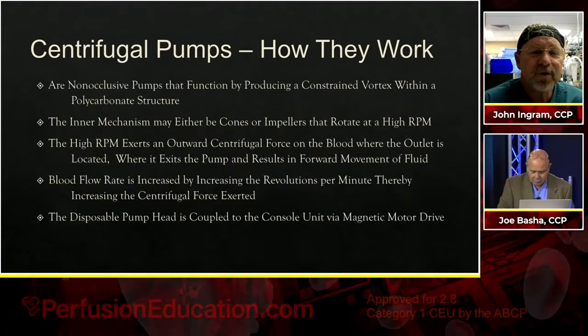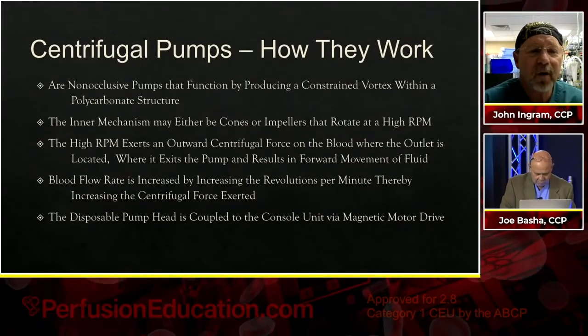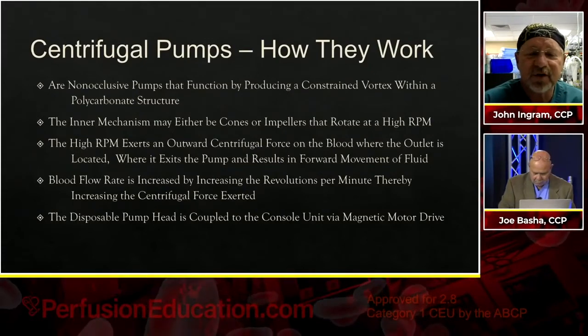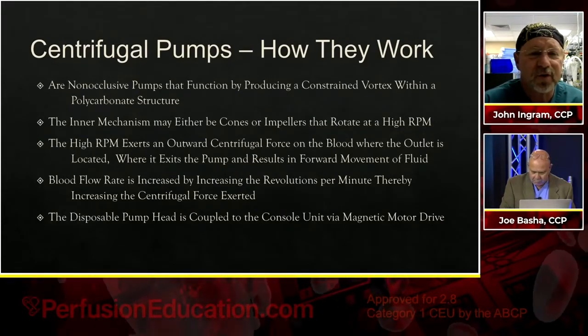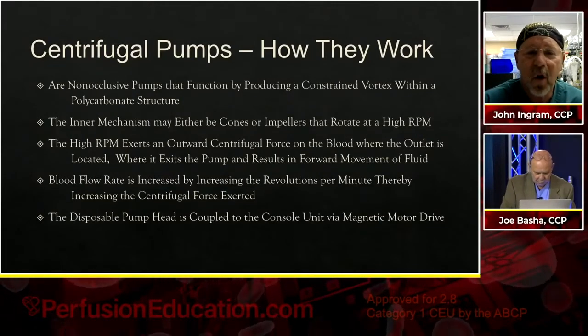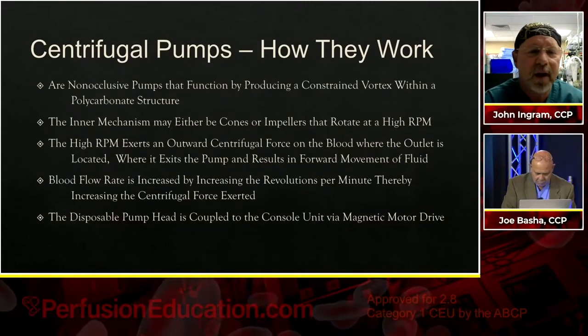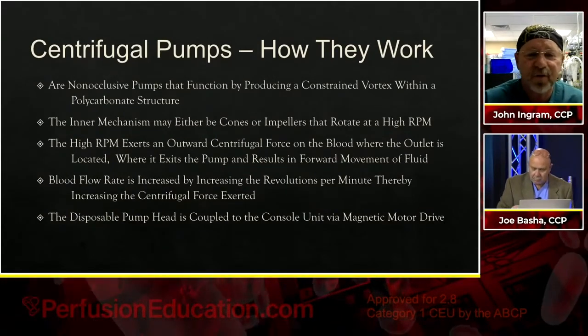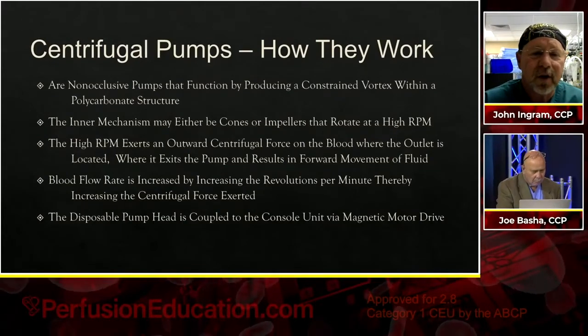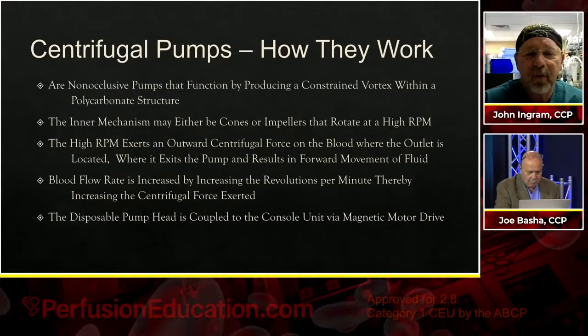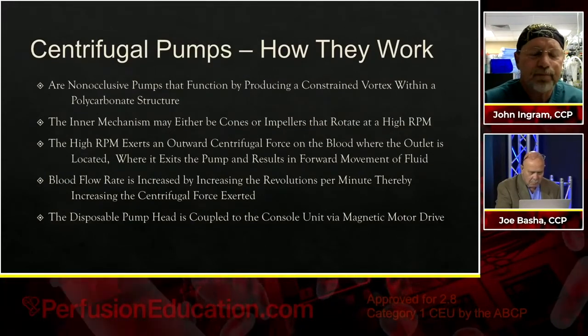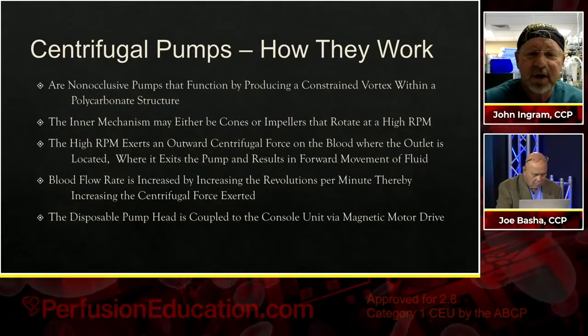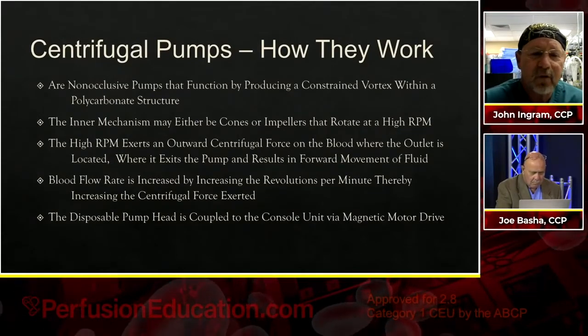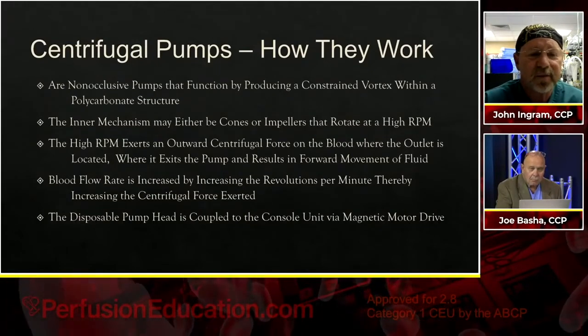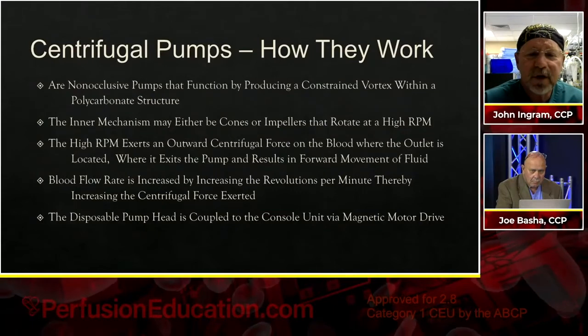Go ahead, Jim. So now, let's talk about centrifugal pumps and how they work. Well, they're a non-occlusive pump and they function by producing a constrained vortex within a polycarbonate structure. The inner mechanism may either be cones or impellers that rotate at a very high RPM. This high RPM exerts an outward centrifugal force on the blood where the outlet is located, where it then exits the pump and results in a forward movement of the fluid. The blood flow rate is increased by increasing the revolutions per minute, the RPM, thereby increasing the centrifugal force that's exerted on the fluid. The disposable pump head is coupled to the console unit via magnetic motor drive.